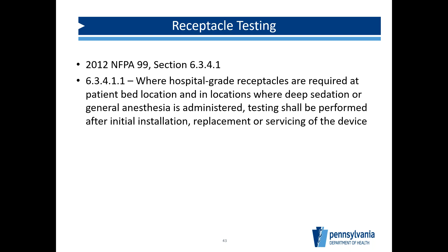Where it gets a little bit different is if you have vent patients and the medical gas piped in system, you would have requirements for hospital grade receptacles in those locations. But in the general rooms, where you don't have vent patients in a nursing home, you could have regular receptacles, not hospital grade. But you'll see here that sometimes we do have the hospital grade, so the requirements are a little bit different for both.